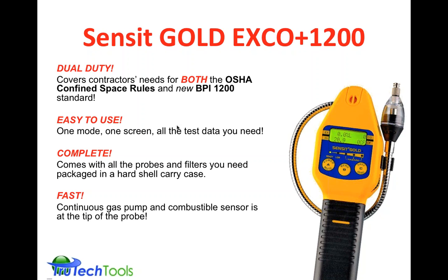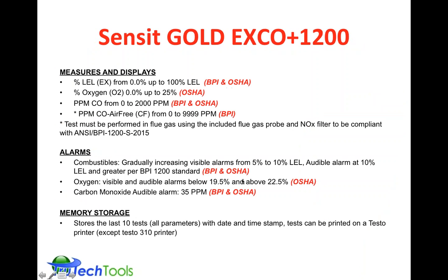There's only one display. It comes with probes and filters, so you can do the confined space entry pre-screening if you need to. It's filtered so it won't absorb water through the probe tip. It's got a hydrophobic filter in it. It's got the NOx filter in it for doing the CO air-free test. Continuous pump and combustible sensor. The sensor's in the tip of the probe, which is a real benefit in that it responds very quickly. That's where the gas is going to hit right there immediately.